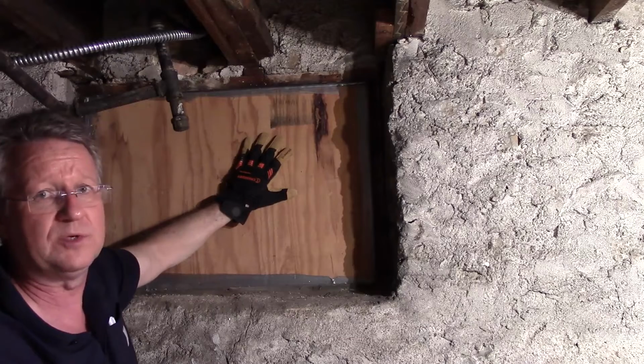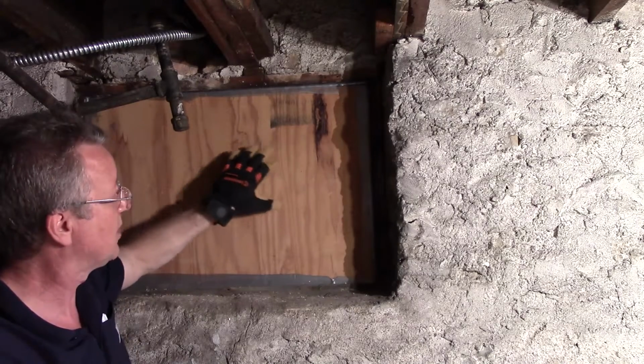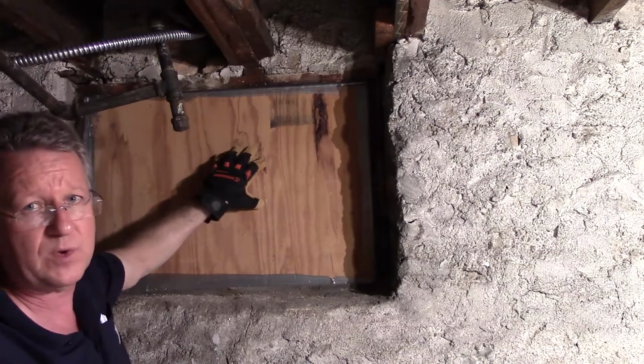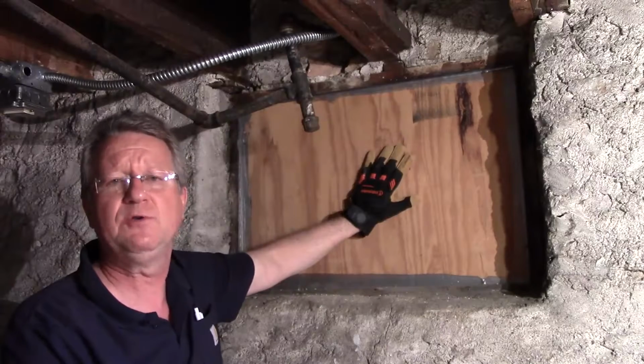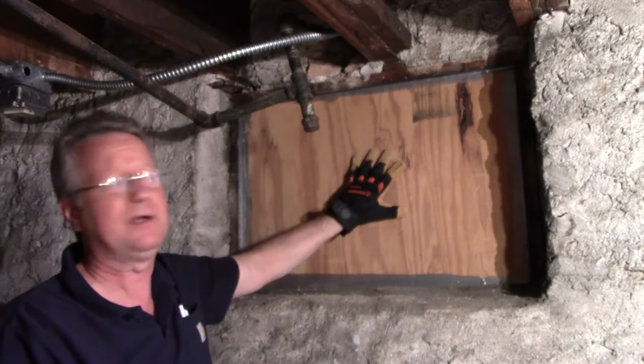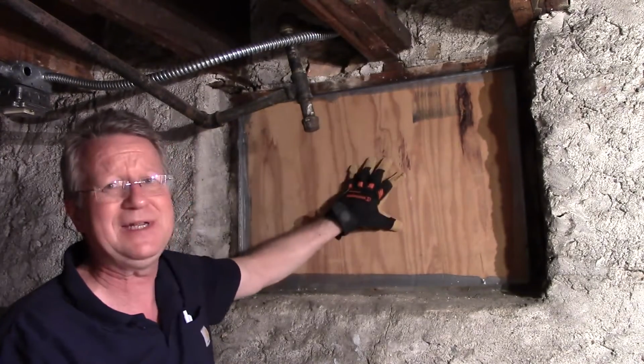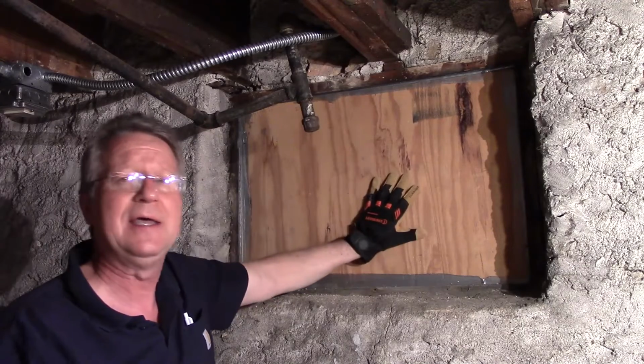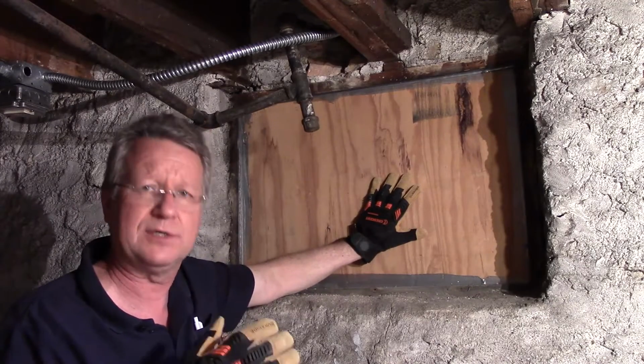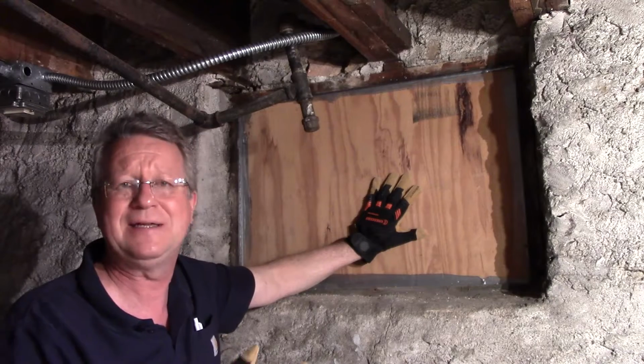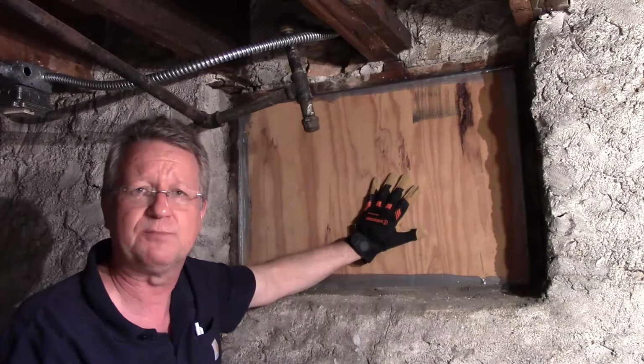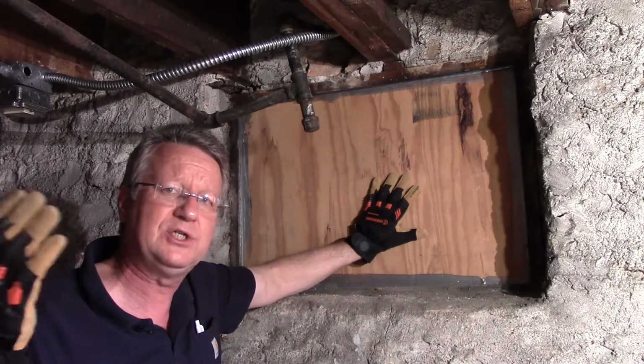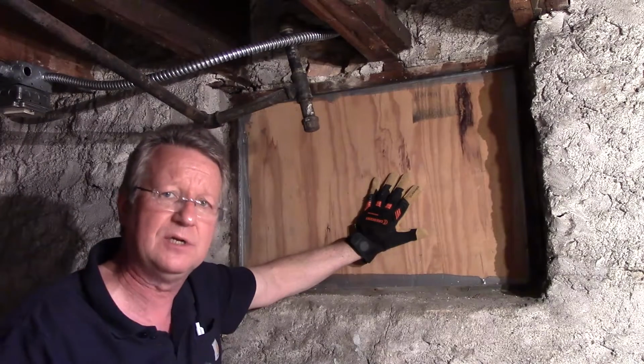This old window was actually covered up, so we're going to be venting this out of 3/4 inch plywood. If you're using a workaround like this and covering an old window, make sure it's completely sealed off with caulk and any openings to the outside are sealed. We don't want to draw in outside air into the crawl space. We want to draw conditioned air from the living space into the crawl space.